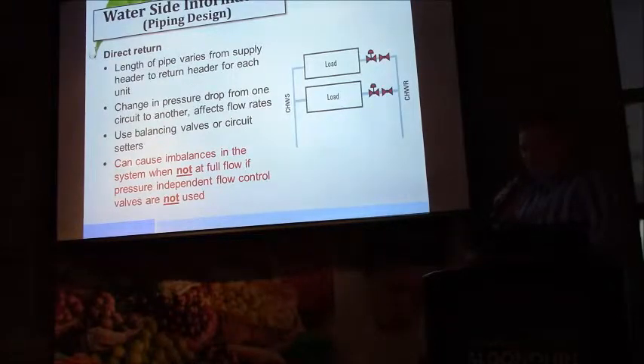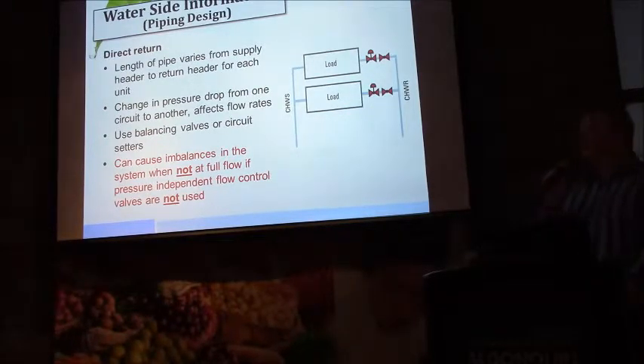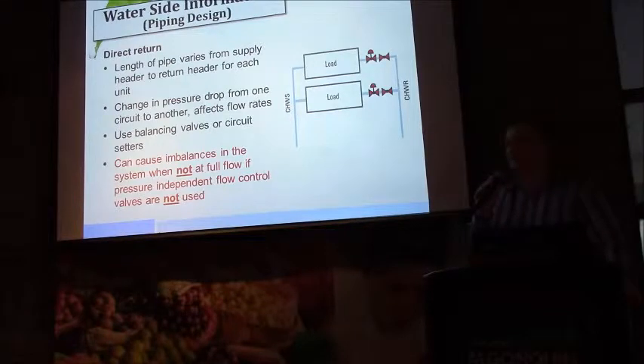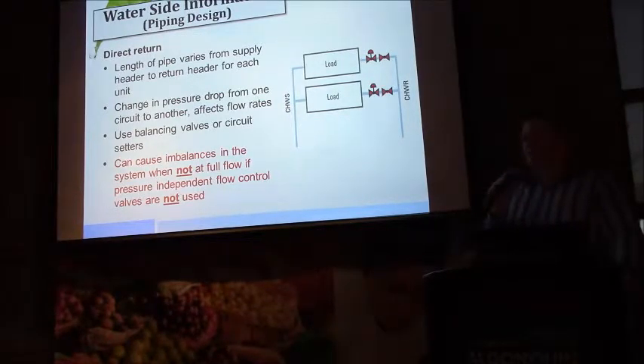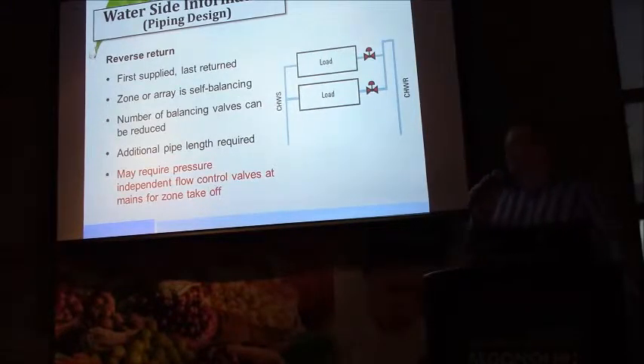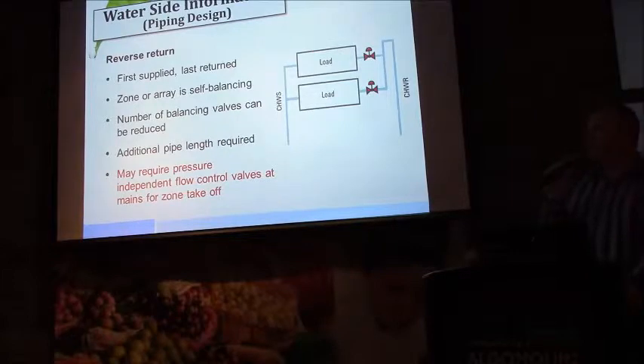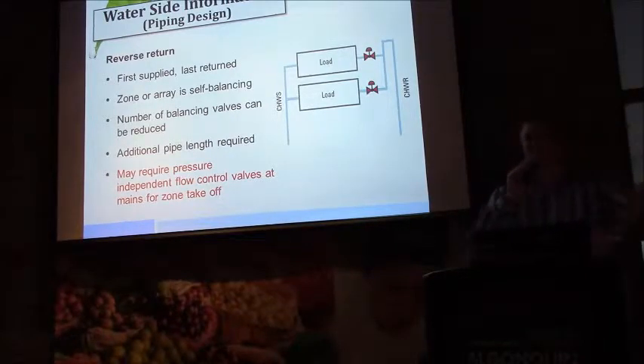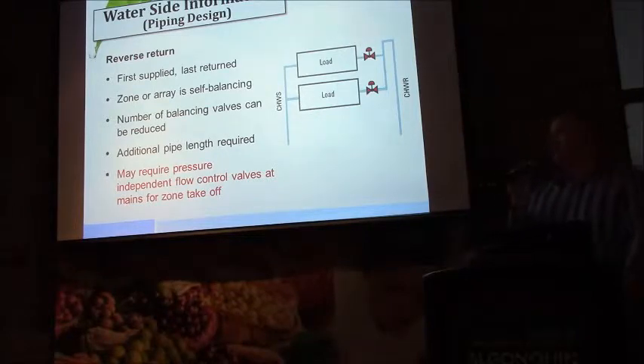Generally, I suggest considering, at the very least, a pressure-independent flow regulating device. And these are available from several manufacturers, but it helps address two issues. One of which, it ensures that the beam will receive at least the minimum flow rate that's required for turbulent flow in the coil and proper operation. And secondly, it really minimizes the balancing effort that's required on the water side.